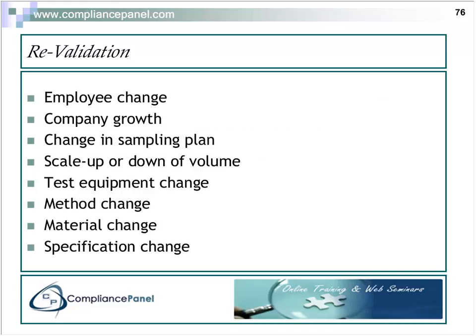Another reason for revalidation is employee change, company growth. We're all of a sudden going to scale up or scale down the volume of product. If we change the sampling plan, we got new test equipment in, new and better and all that kind of stuff. Newer is not always better. If we change our production method, if we change our production material, if somebody decides the specification is not right and wants to change that, that may be, only may be, a reason for revalidation. We need to consider it.